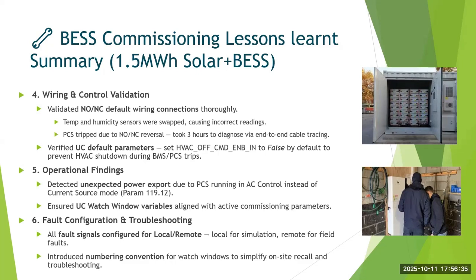What happened because of it? When I started commissioning the PCS, it was starting, ramping up and tripping. When we analyzed, we had to go to the electrical drawing and check cable by cable, wiring, continuity. Then we found that the NO/NC contactor wiring was wrong. To detect that, we took 1 day, shutting down everything and checking each and every parameter. That itself took a lot of time. Those things can be avoided if we have a proper checklist, ensuring that each and every cable, connection, NO/NC, everything is properly connected.